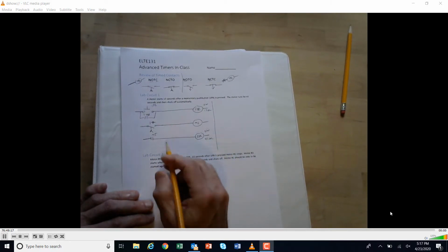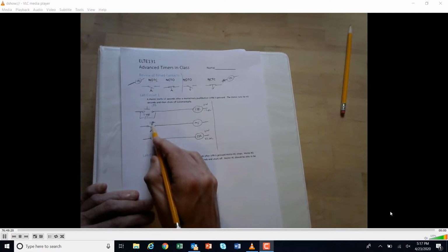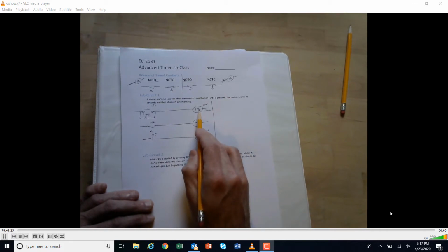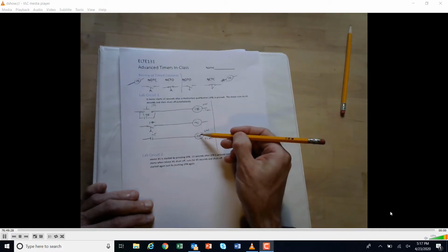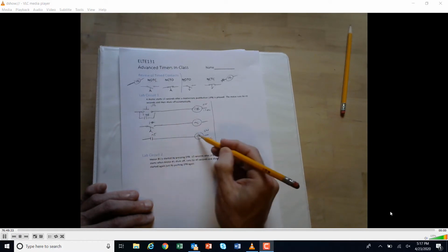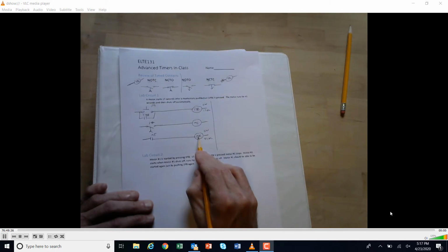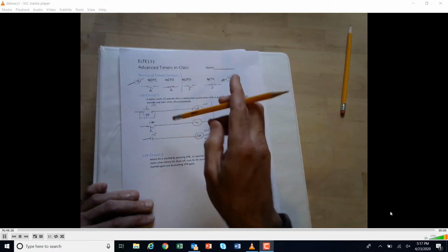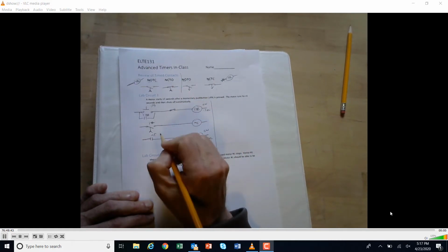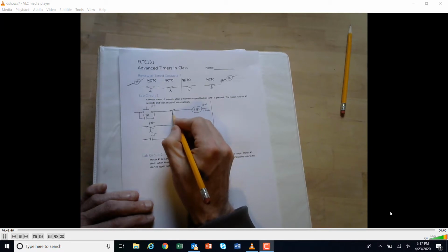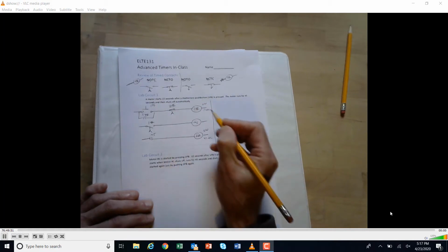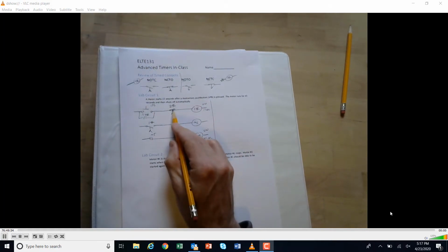Okay. I could have used this same contact, or another one of these instances of the contact here, because basically the timed relay came on, and 15 seconds later I need this to come on and this to come on. So I could have used that. But hey, if this comes on, it closes that and starts that. So this goes 45 seconds. And what do I want to do with that? Well, I want a normally closed contact here, and I want it to open after 45 seconds.